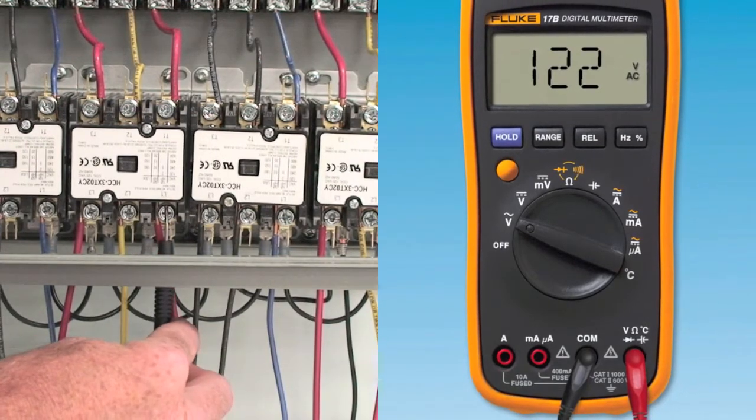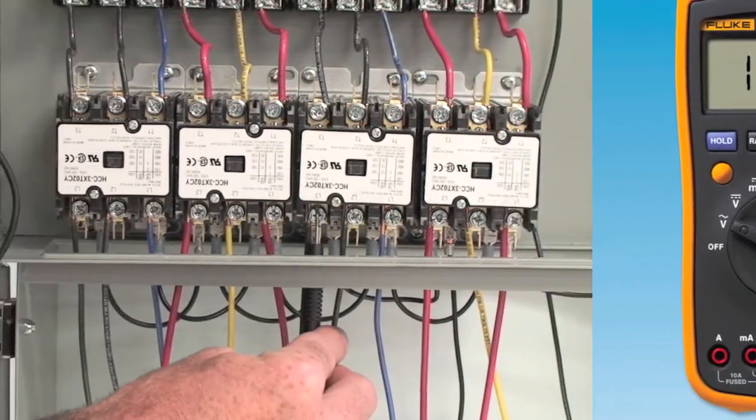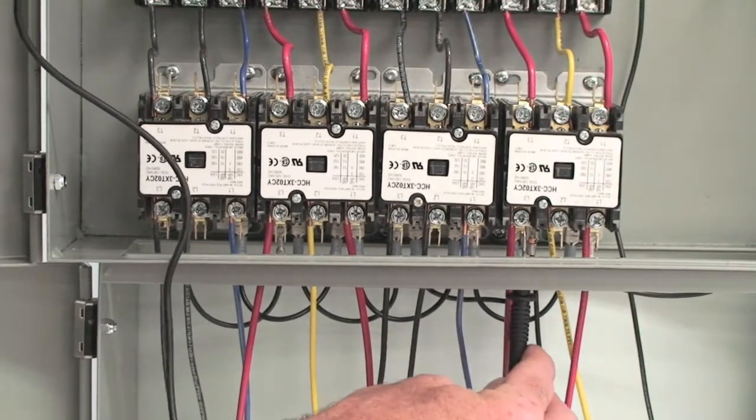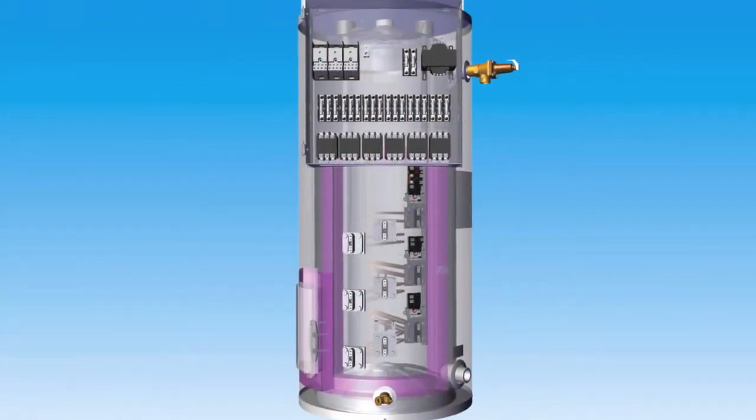If expected AC volts are not measured on either L1, L2, or L3, verify ECO is closed and thermostat is calling and replace corresponding contactor. Refer to parts manual for part numbers.